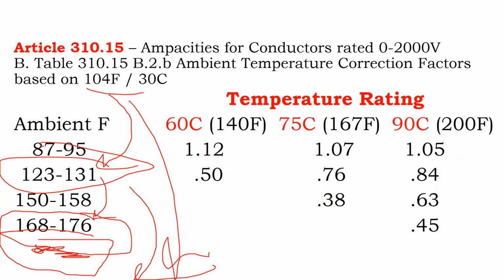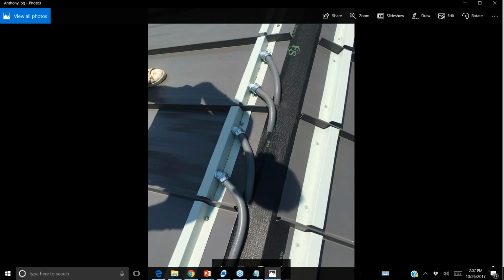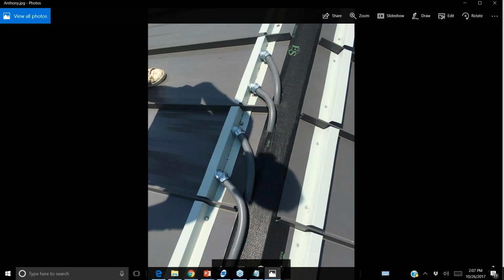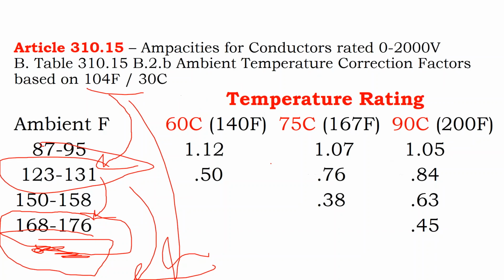And what that says is in Phoenix, Arizona, where you get into 120 degree ambient days and it can be 190 up on your rooftop, it's a really bad idea to have any kind of wires being within 1 inch of your roof surface. And for that matter, something like this wouldn't work in Phoenix, Arizona, because by the time we're within 1 inch of the roof surface, we're not finding any cables that are large enough to handle the additional temperature rating.